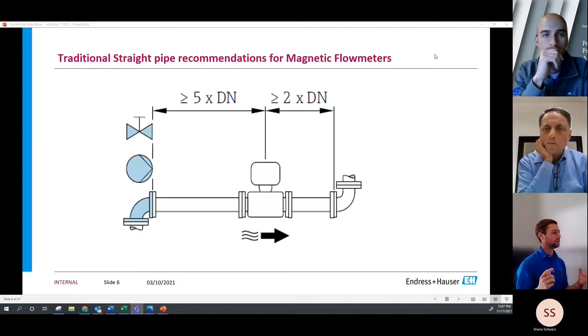And what happens when there's turbulence in the pipe is that the voltage that's induced gets disturbed, and then the signal that's uptaken by the transmitter itself becomes what we call noisy or inaccurate, and therefore you get a lot of chatter in your signal output. It's a common enough issue that E&H put a lot of R&D into. You know, what is a solution going to look like?